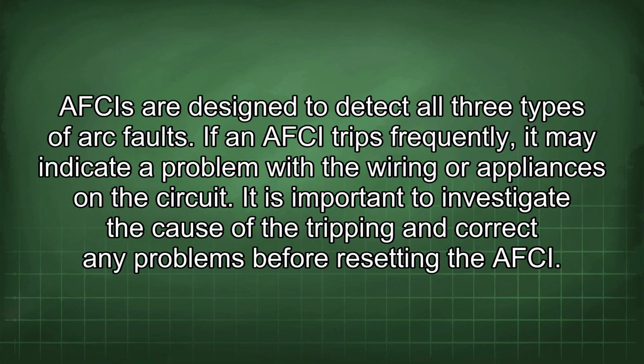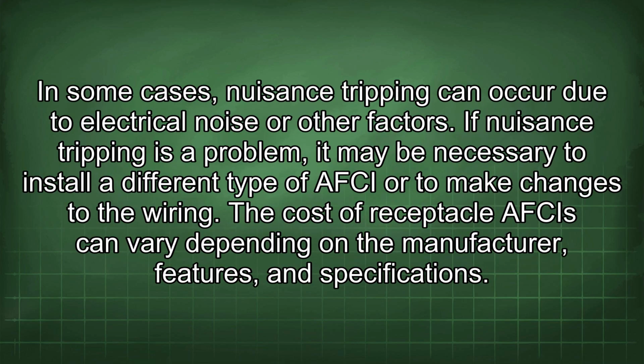AFCIs are designed to detect all three types of arc faults. If an AFCI trips frequently, it may indicate a problem with the wiring or appliances on the circuit. It is important to investigate the cause of the tripping and correct any problems before resetting the AFCI. In some cases, nuisance tripping can occur due to electrical noise or other factors.